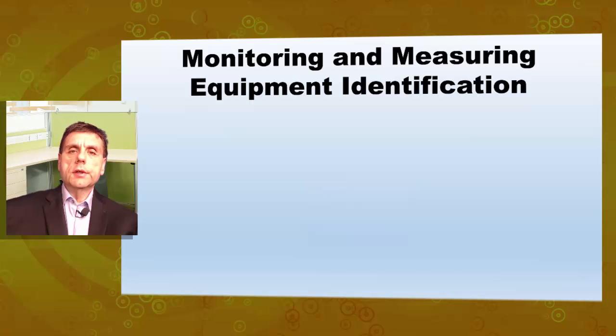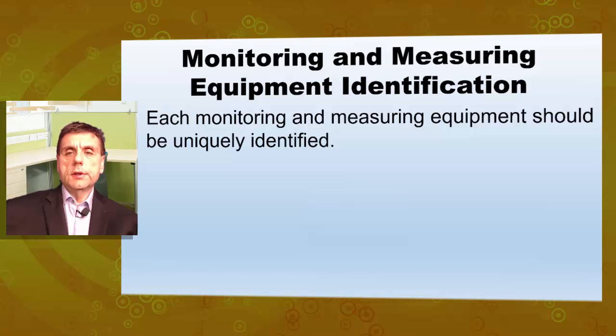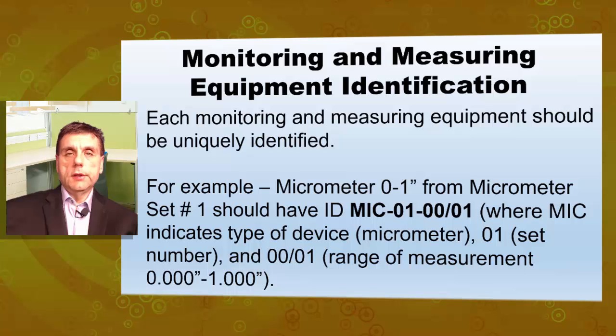Okay, monitoring and measuring equipment identification. Each monitoring and measuring equipment should be uniquely identified. For example, if we have a micrometer that measures from 0 to 1 inch from micrometer set number 1, we should identify it with the example provided here, which is MIC-01-00/01, where MIC indicates the type of device, which is micrometer in this case. 01 is a set number, from the set number 1, and 01 indicates the range of measurement of the measuring instrument, which is from 0 to 1 inch. This is just an example.